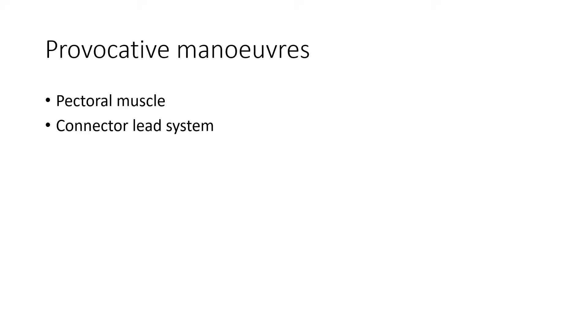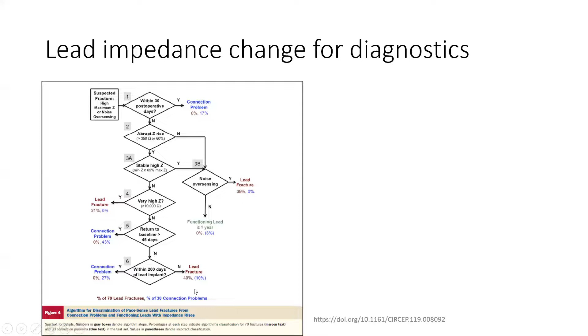Now, this was the algorithm given by Swerdlow et al. in utilizing the impedance change for the diagnosis of a conductor fracture versus a connection problem. If the occurrence is within 30 post-operative days with an abrupt impedance rise and a gradual return to baseline, or more than 45 days, then it is more likely a connection problem. However, if the abrupt impedance rise is associated with noise oversensing or a very high impedance, which is more than 10,000, then it is more likely a lead fracture.